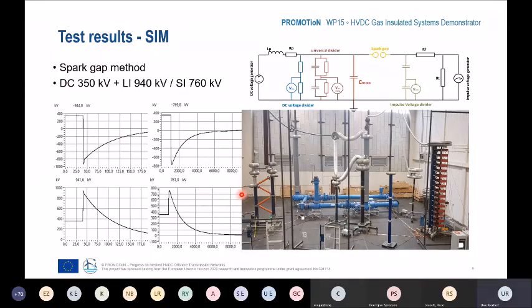You could see here one example of the test setup. Again, a picture of the test setup. That is the test setup, the DC source and the impulse source in the lab in Arnhem. And the test circuit shown here. So we have used a spark gap to connect the impulse source to the test device. And you could see here some examples of the superimposed voltage stress. So we have used all combinations, so polarity combinations and lightning and switching impulse combinations with a rating of DC 350 kV, lightning 940 and switching 760 kV. For lightning and switching, the values for on-site tests of a GIS were chosen, so that is equal to 80% of the nominal value.